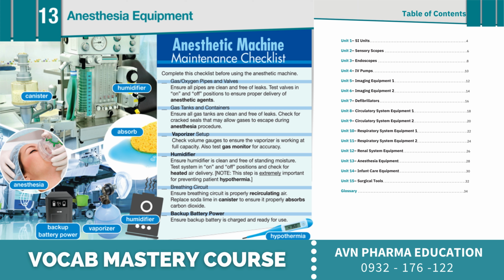Unit 13. Anesthesia Equipment. Exercise 5, page 29. Anesthetic Machine Maintenance Checklist. Complete this checklist before using the anesthetic machine. Gas, oxygen pipes, and valves. Ensure all pipes are clean and free of leaks. Test valves in on and off positions to ensure proper delivery of anesthetic agents. Gas tanks and containers. Ensure all gas tanks are clean and free of leaks. Check for cracked seals that may allow gases to escape during anesthesia procedure.